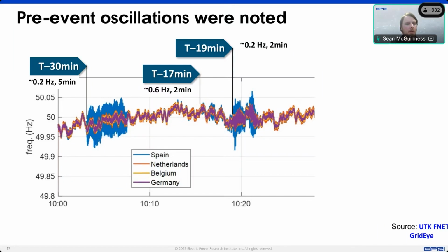So an oscillation in frequency can happen, but you do have to push the grid outside of its normal frequency range in order for protection to actually operate and disconnect devices, or for the oscillation to result in the voltage going out of normal operating range and voltage protection operating. So the oscillations were present. However, it's important to emphasize that you need other parameters to go outside of operating ranges in order for a device to trip and to trigger a cascade tripping.